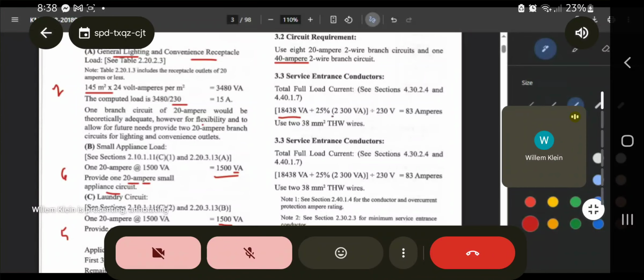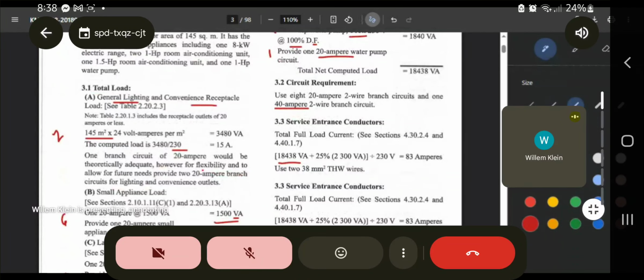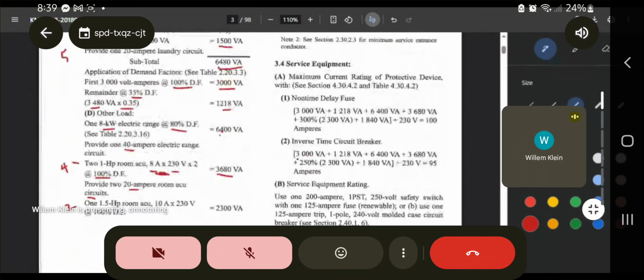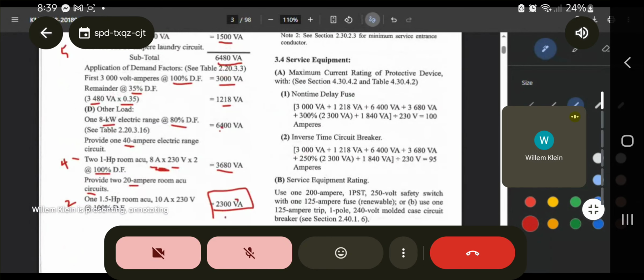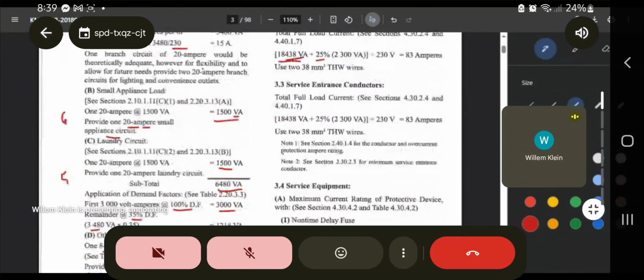So your highest rated motor is still the 1.5 HP. Okay, this one. So let me just double check the computation that was used. So that should be 2 times 2.5 plus 18438 divided by 230. Okay. I think this is what happened here. So if you're wondering why it's 25%, okay, let's clarify this one. If you look at the 18438 VA, that is already the total of all your load, including this one. Okay, so this is already included in the 18438.